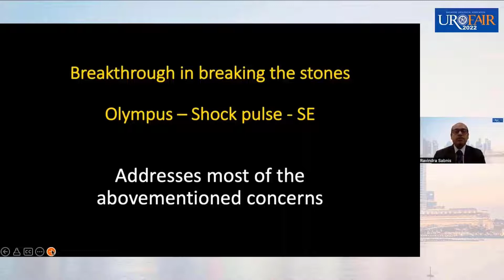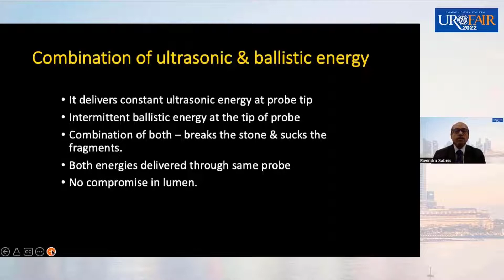And now shock pulse has been introduced, and it is considered a breakthrough in breaking stones because it addresses most of the above mentioned concerns. Let us see what they are. First of all, what is shock pulse? Shock pulse is a combination of ultrasonic and ballistic energy. It delivers a constant ultrasonic energy at the probe tip, with intermittent ballistic energy at the tip of the probe, and the combination of both breaks the stone and sucks the fragments very effectively. The beauty of this device is that both these energies are delivered through the same probe. So there is no difference like in LithoClast Master, and therefore there is no compromise in the lumen. A large lumen is available for sucking the fragments or the powder, whatever you make.